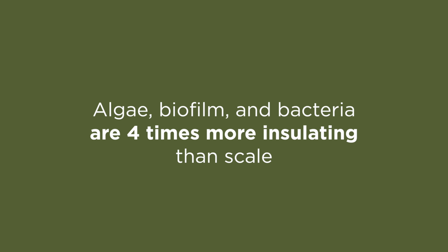Two, bacteria is a huge insulator. Remember when we talked about scale being an insulator, that every eggshell's width of scale leads to 12% energy loss? Algae, biofilm, and bacteria are 4 times more insulating than scale.